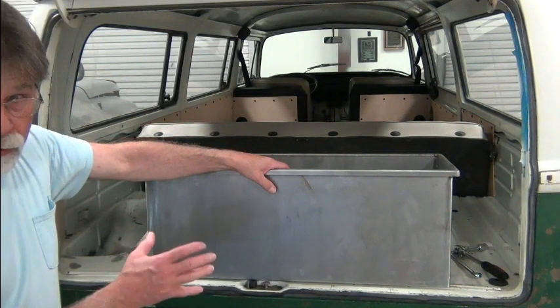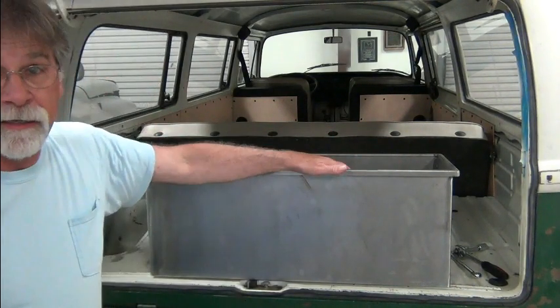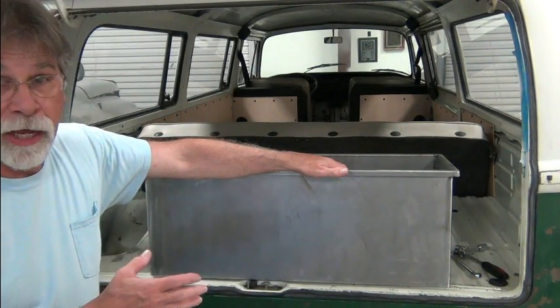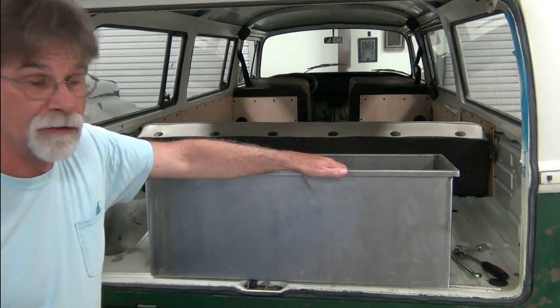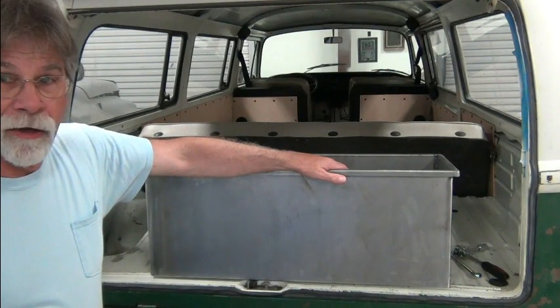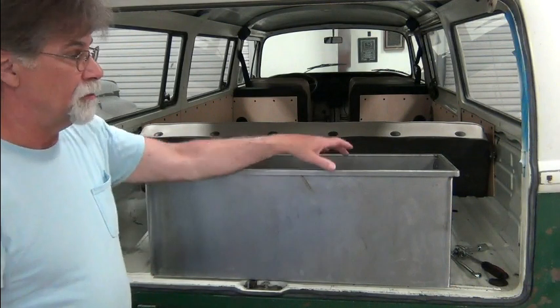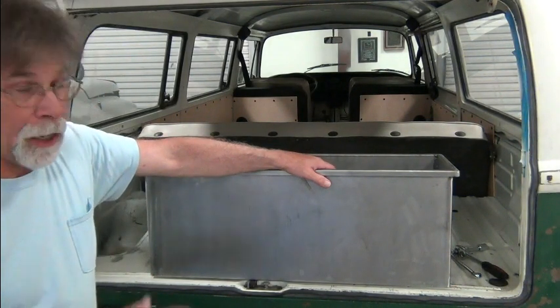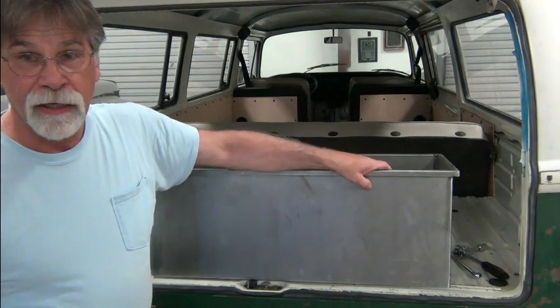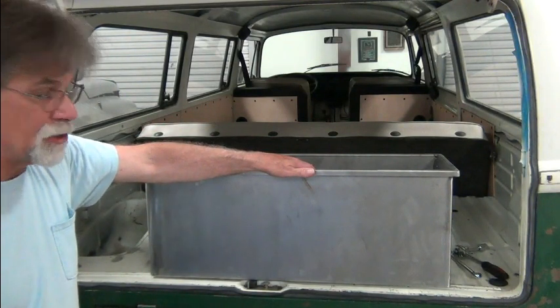What I'm going to be doing today is test fitting. I've already test fit to make sure that the cells fit in — that part was good. Now I'm going to double-check that the OD fits into our space, and also prepare for the mounting. There's additional welding going to be done to these to allow us to mount them in the vehicle securely, and we'll be punching holes in these for our cabling. Next we're going to check the fitment.